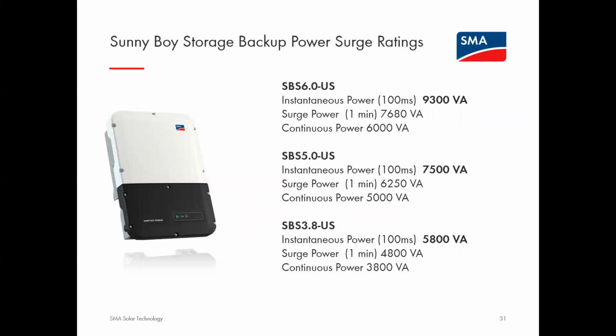One of the really unique things about SMA's AC coupled architecture, as I was telling you before in that slide comparing hybrid DC coupled systems to AC coupled systems, is that Sunny Boy Storage is able to deliver a tremendous amount of power. For example, the Sunny Boy Storage 6 kilowatt version, 6.0, although it's rated at a continuous output power of 6 kilowatts, is capable of surging to 7.68 for a full minute. And for short duration bursts, 100 milliseconds or so, it can surge up to 9.3 kVA. So it's really a great solution for backup power loads where you have a high inrush current.